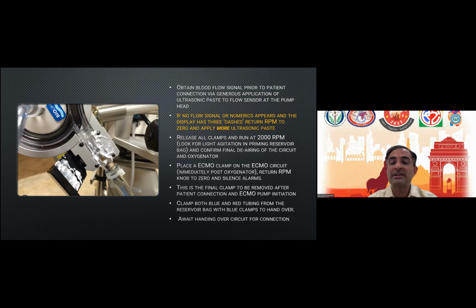Release all the clamps and run the ECMO at about 1500 to 2000 RPM, and look for any air bubbles, any agitation, etc., to ensure that there is smooth flow of the saline or the prime fluid within the ECMO circuit. Once all this is set up, place an ECMO pump clamp on the ECMO circuit, which is immediately post oxygenator, and return the pump to stationary or 0 level, and keep the alarms silent and ECMO ready to go.